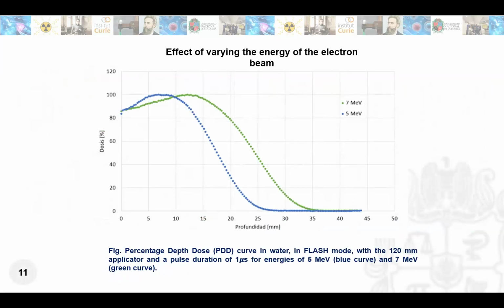Effect of varying the energy of the electron beams. This figure presents a comparison of the percent depth dose PDD curves for 5 MeV and 7 MeV electron beams using a 120 millimeter applicator and a pulse duration of 1 microsecond in FLASH mode. When all parameters are kept constant except for the beam's energy, it is observed that the maximum dose depth, as well as R90 and R50, are reached at greater depths with the 7 MeV green curve compared to the 5 MeV blue curve. As expected, lower energy electrons have reduced penetration in tissue.